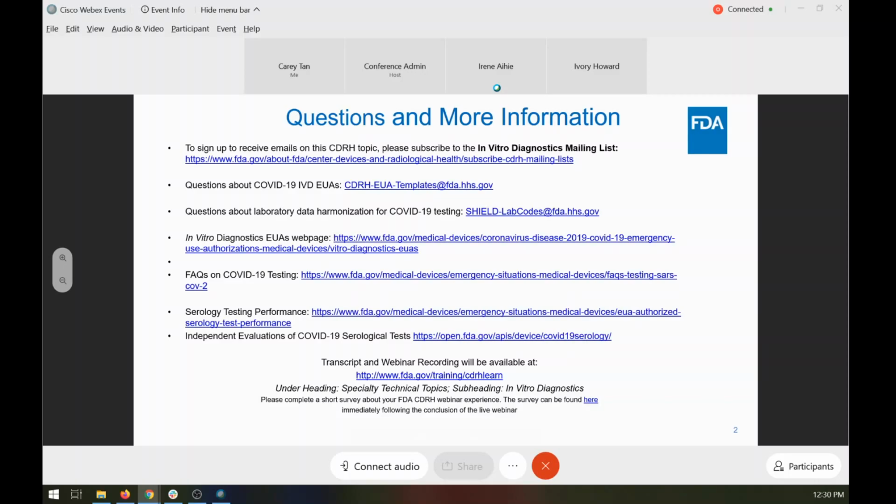Hi, good afternoon. My name is Gustavo Higuere, and my question is in reference to using a real-time PCR equipment to do the reference panel validation. We're trying to help a Chinese company called Sansure Biotech comply with the required reference panel. As such, we have a question regarding the devices that may be used to perform the test. We have at our disposal an ABI 7500 Fast DX real-time PCR instrument and a SLAN 96P real-time PCR system. However, the IFU in the EUA mentions an ABI 7500 real-time PCR system. Is it possible to perform the reference panels using the ABI 7500 Fast DX real-time PCR system or the SLAN 96 real-time PCR system, as we do not have access to the one mentioned in the IFU?